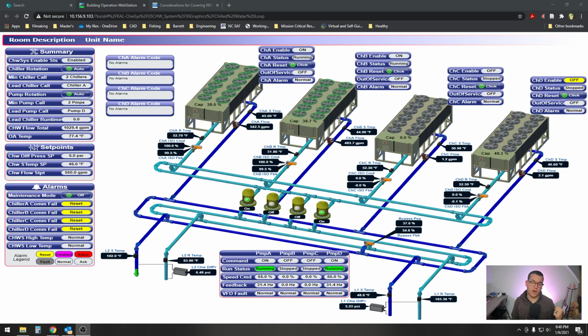The first one is the pumps and moving water through the system. Water has to be moving through the system, obviously, to remove the heat from the data center. Formerly we had one pump per chiller, and they were just flowing 100% all the time, which is not energy efficient at all. So we changed it to a variable primary system. As explained in the last videos, a variable primary system is the primary pumping of the system, and we can vary the speed, vary the flow at which it operates.